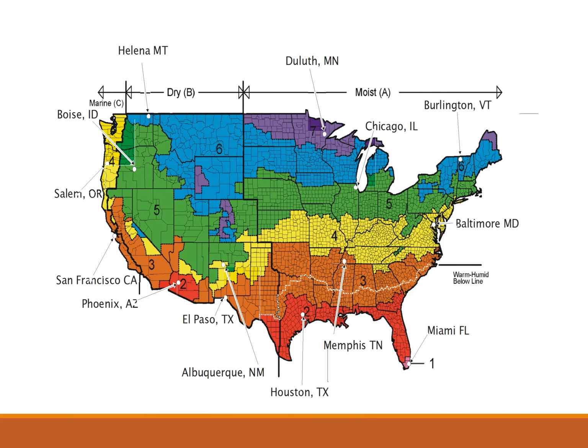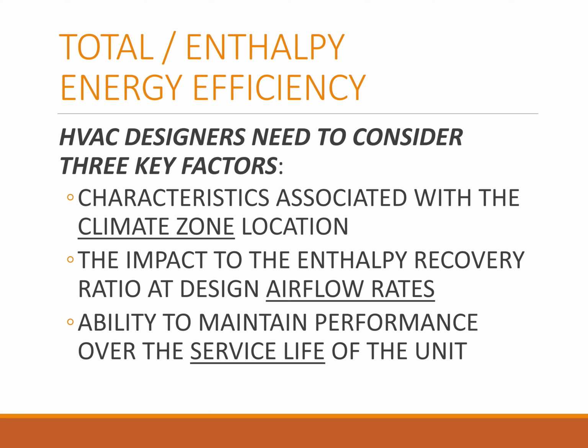When looking at this map again, different climate zones may be better for different types of energy recovery products or media. Keep these considerations in mind when planning your equipment for projects in these zones. The key factors to consider from a design perspective are the climate zone in which the project is located, and the airflow rates in CFM. Uneven airflow rates will have an impact on enthalpy recovery ratios and may lead to a more difficult time in reaching standard or code requirements.